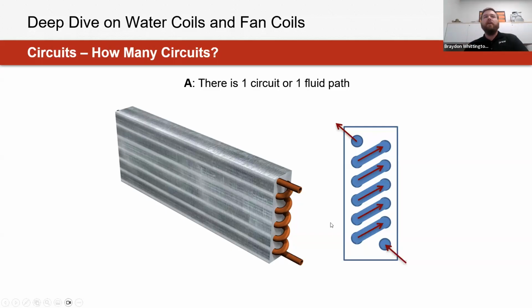A lot of the times, and I've seen a couple of you say it, people interpret circuits as fluid paths by just counting how many connections or entry points are going into that coil. But what you'll actually see is that this is just one individual tube passing back and forth through that coil before the fluid leaves. So that's how it dictates the circuit count for that coil.